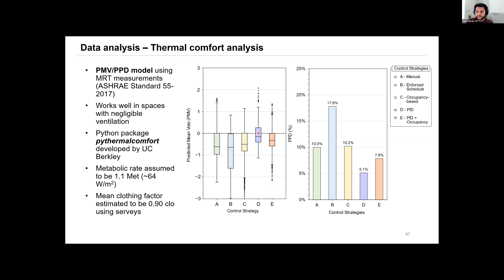We found that with an enforced schedule from 8 to 5, most people are dissatisfied, go figure. But with occupancy-based or temperature-control-based approaches, people were generally more satisfied, because 72 degrees means something different to different people. Each person set their own temperature set point to whatever they wanted, and they were more satisfied that way.